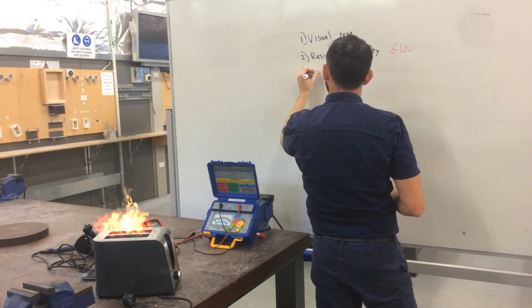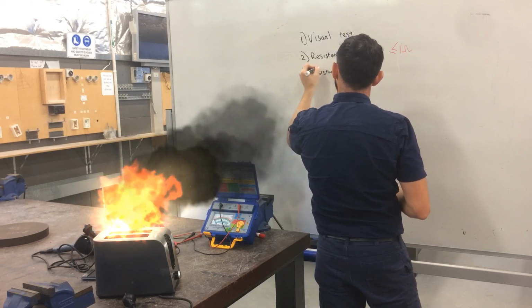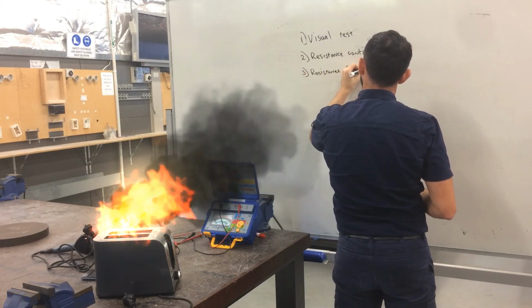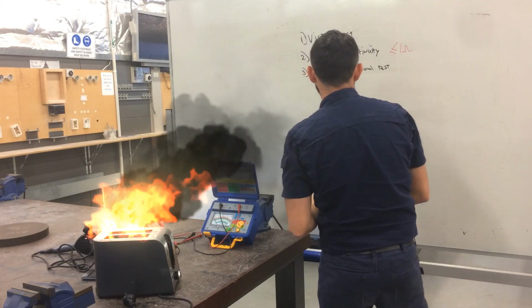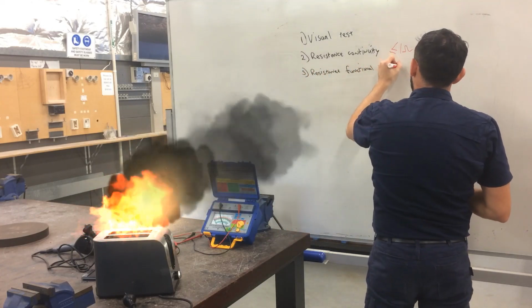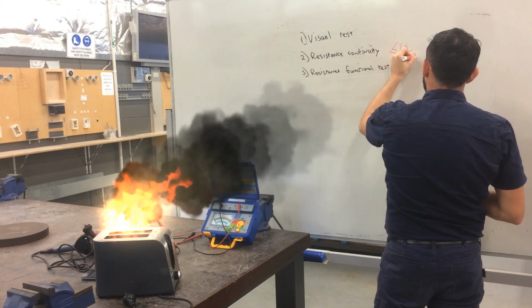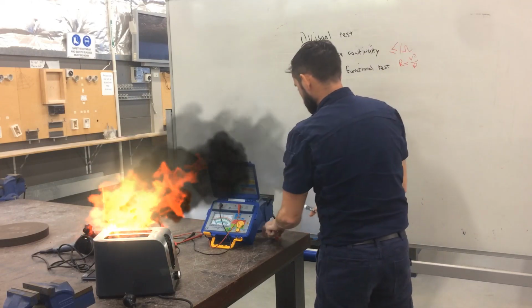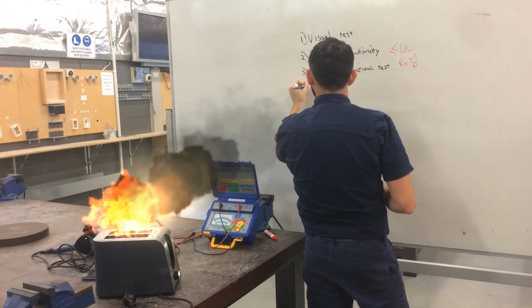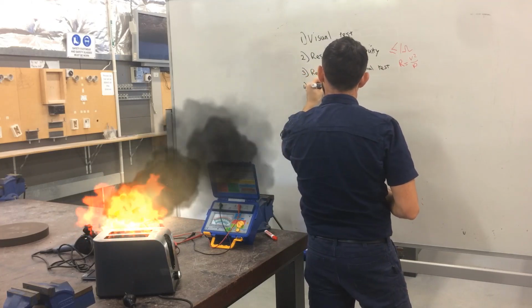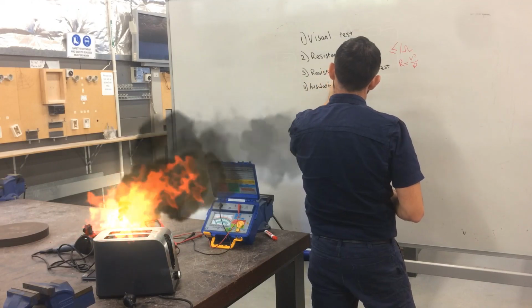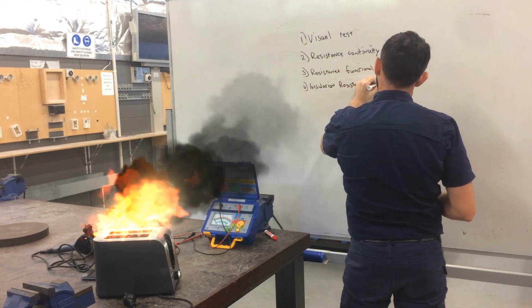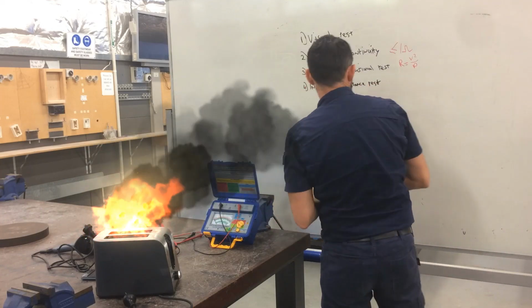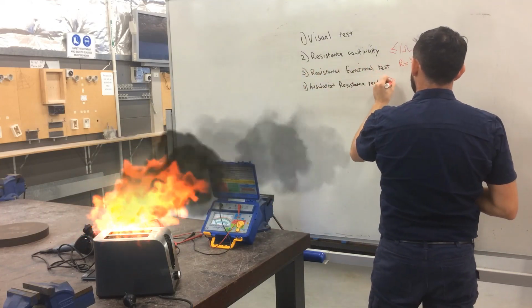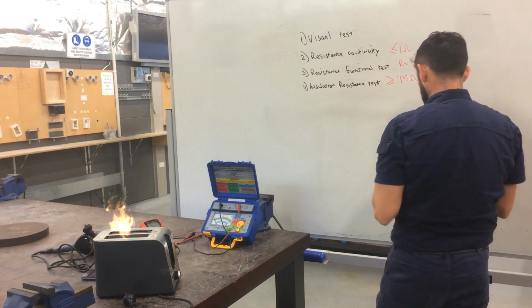And then we did the resistance functional test. Now the value we were looking for there was what we calculated using a power formula, R equals V squared divided by P. And then we did our insulation resistance test. Now the value we're looking for was greater than or equal to 1 mega ohm.